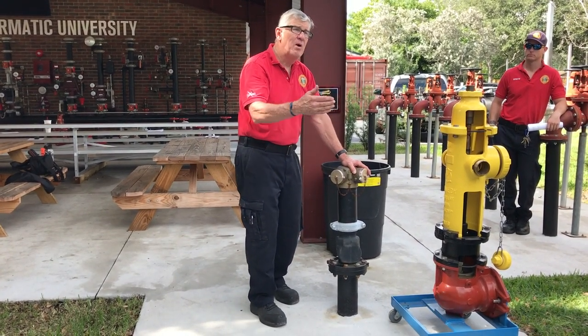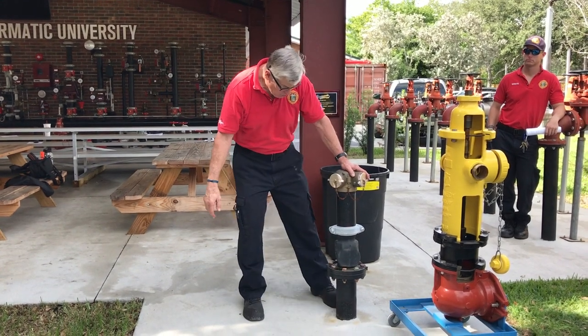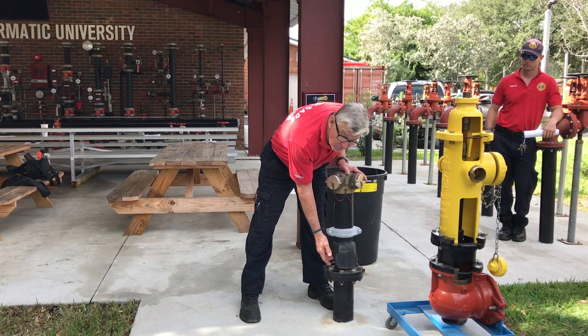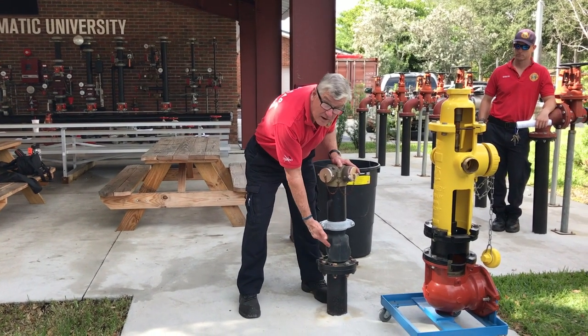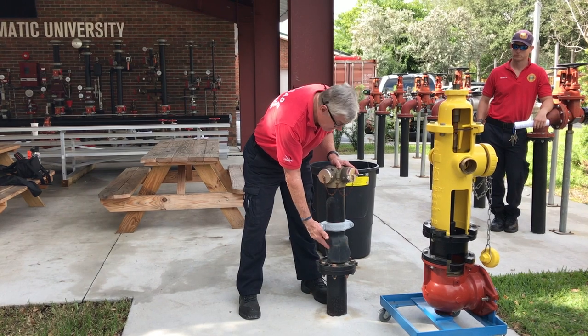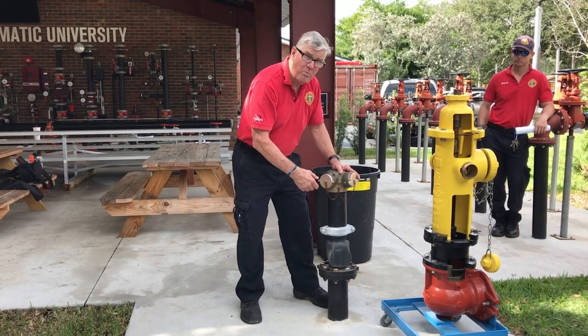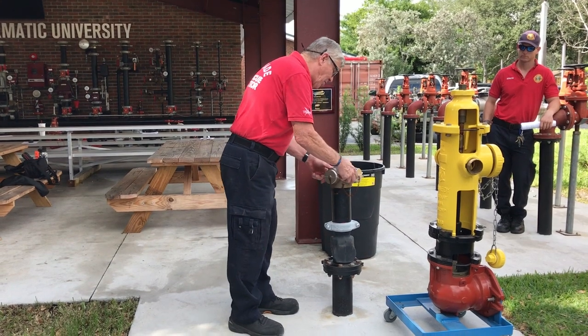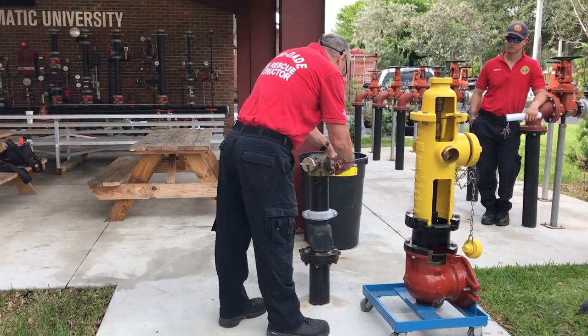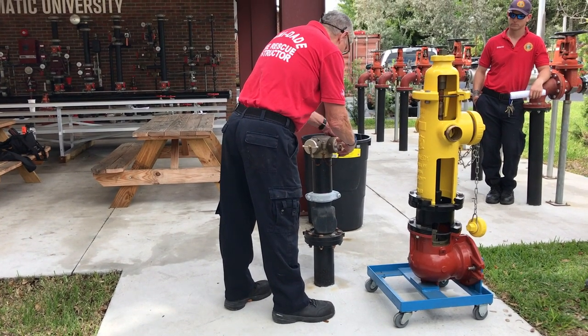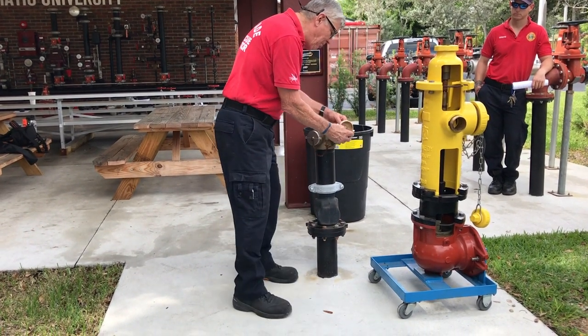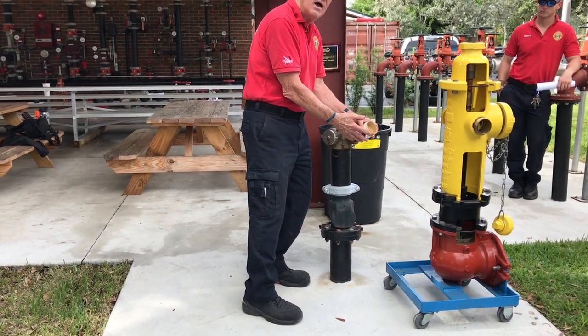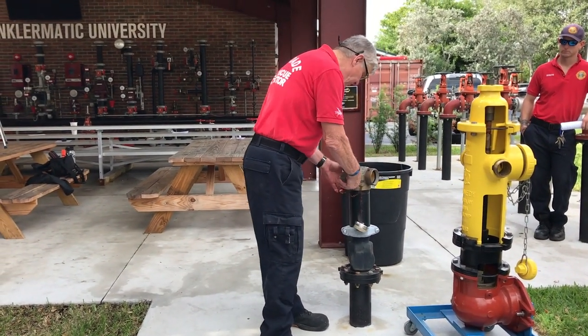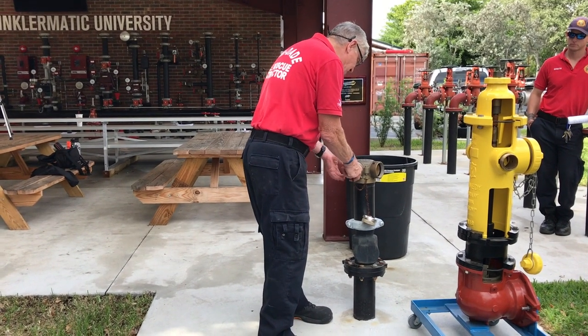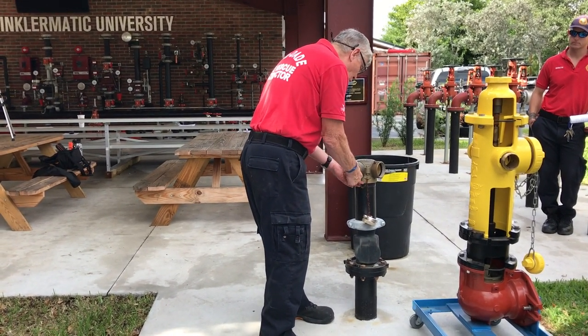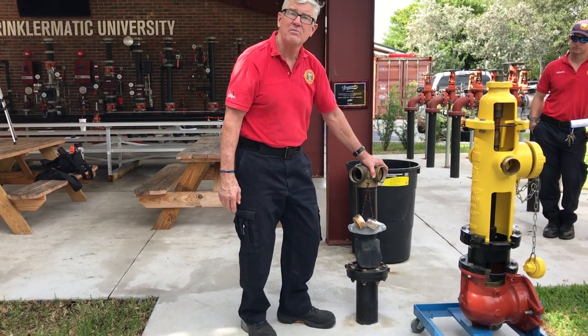Conversely, if you pump less than system pressure, you will fail to open this check valve. You will have system pressure up to this point. If the system pressure is 250 and you pump 150, you will fail to open the check valve. There is a clapper inside of this connection. And as firefighters, when we have plugs, and a plug is nothing but a male cap with male threads, if you have intentions of putting two lines into an FDC, take them both plugs out at the same time.